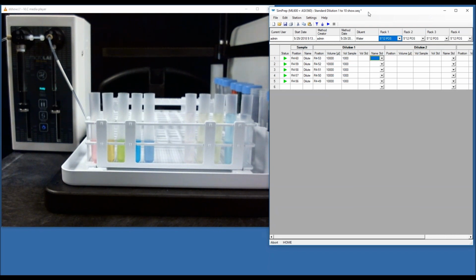Another question just came in. Any routine maintenance needed? There's very little. Honestly, if you run an auto sampler, you should be aware of most of the maintenance required. If you're rinsing normally, it shouldn't be a big problem. The probes do eventually wear out. They wear out faster if you forget to remove the caps from your 50 ml vials, of course, but they will eventually wear out. And we recommend those being changed out on a yearly basis, but it really depends on how well you take care of it.